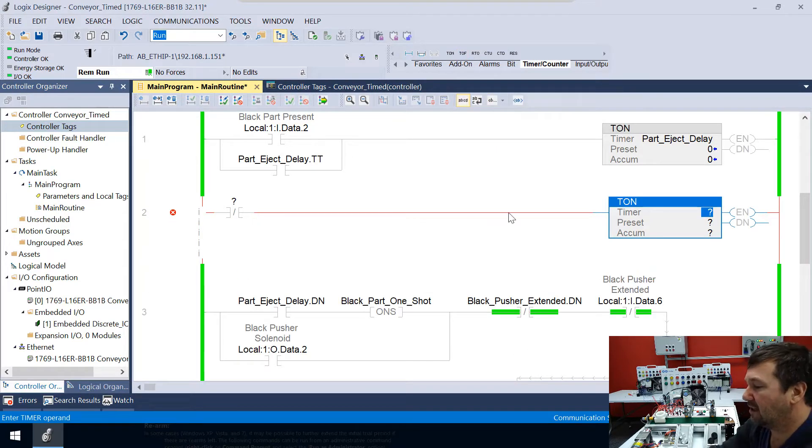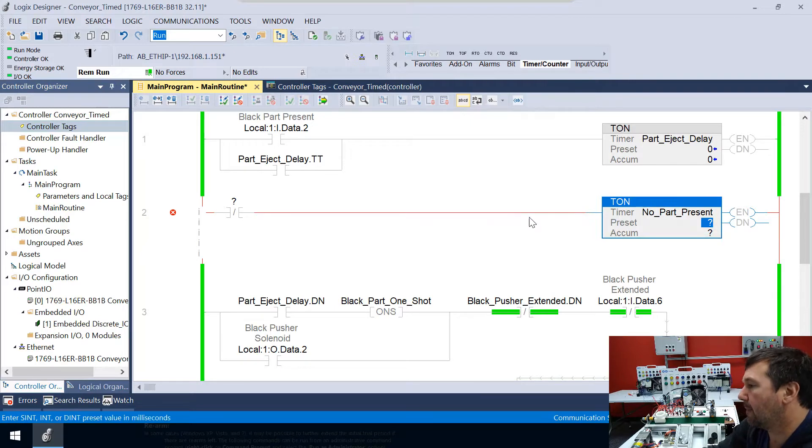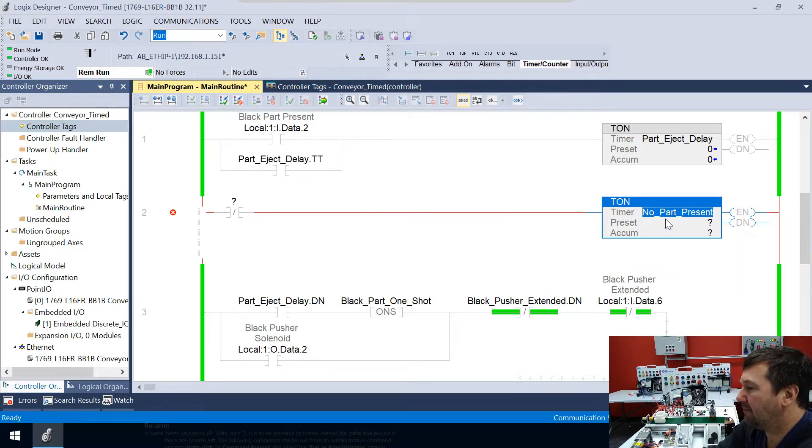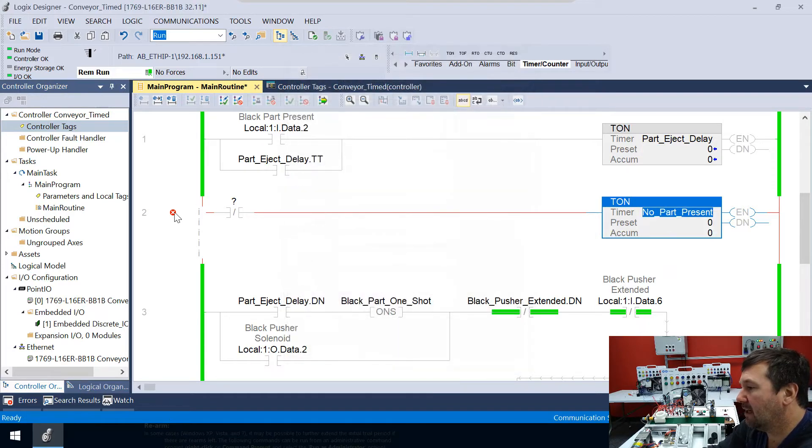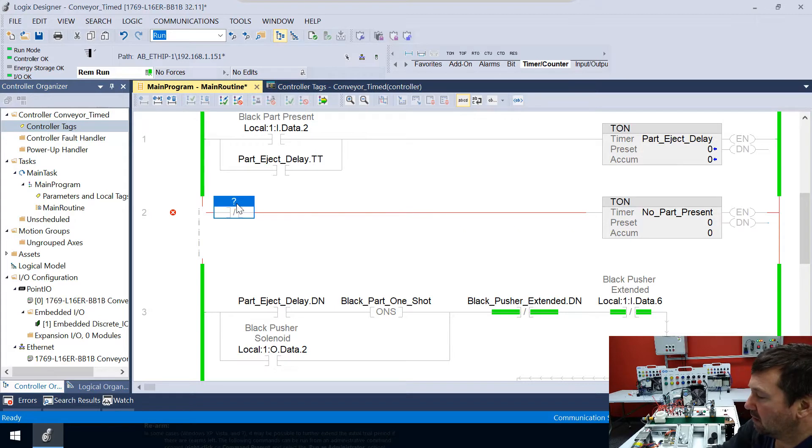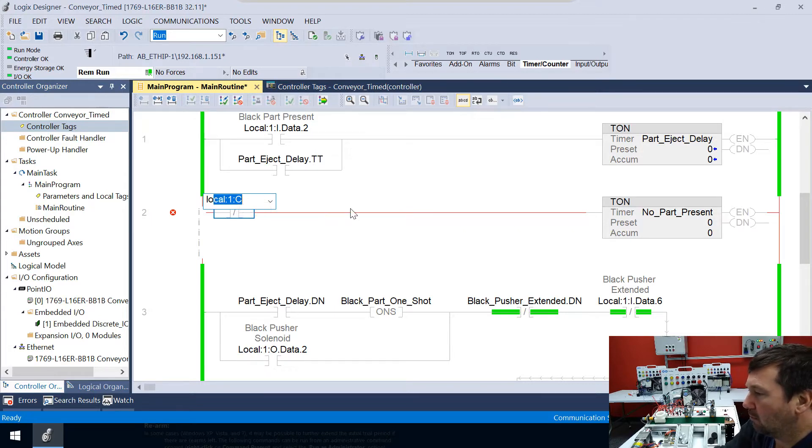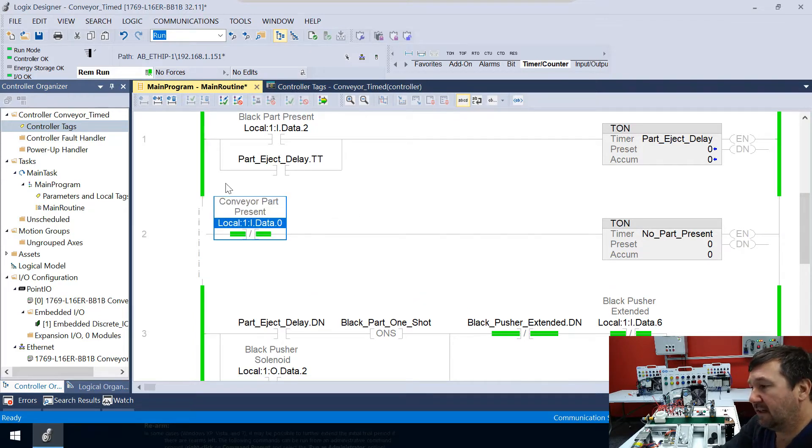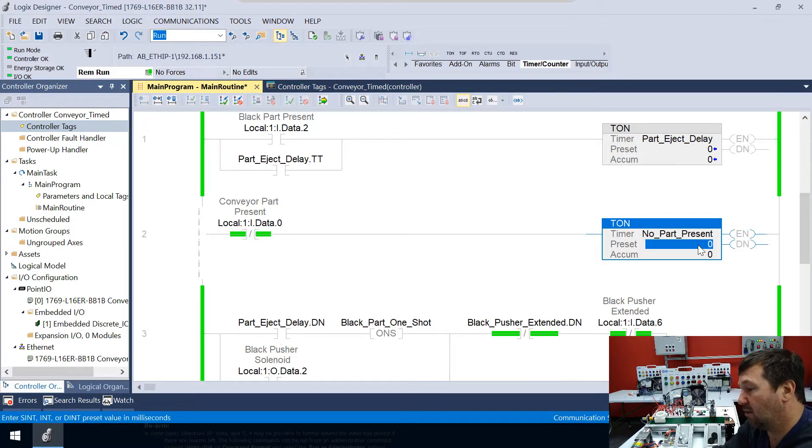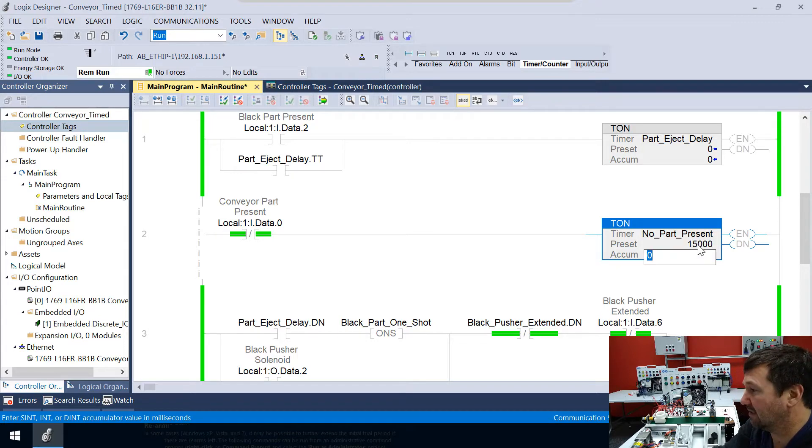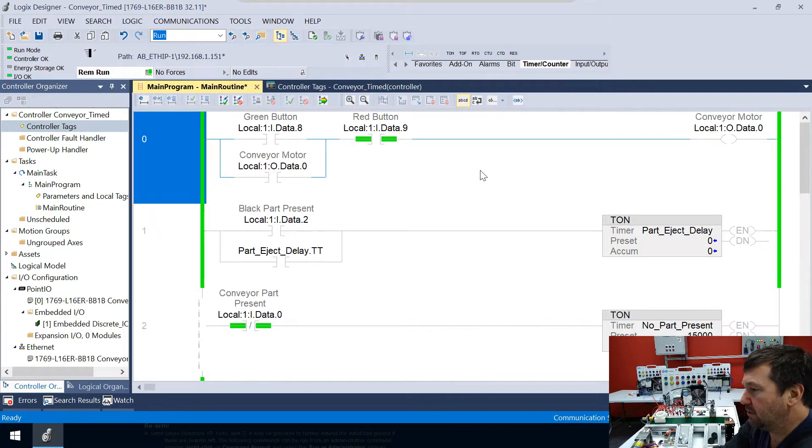And the examine off is going to start a timer. So we'll get our timer tab. We'll look for a TON. And let's call this timer No_Part_Present. And we'll create that one. And it will be a type of timer. And oh, I forgot to put an address here. But yeah, that would be important. In this case, we're going to look at Local:1:I.Data.0. And that's our conveyor part present. And I said I wanted 15 seconds. So that would be 15,000 milliseconds.